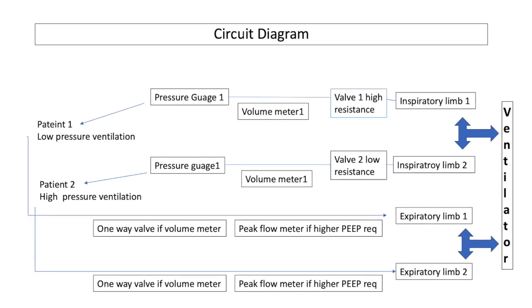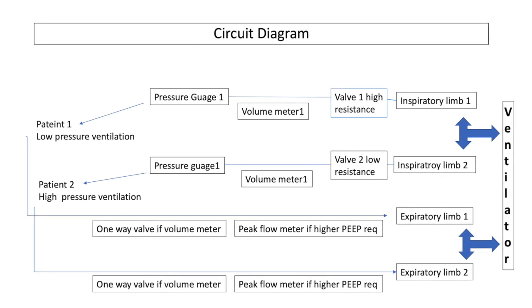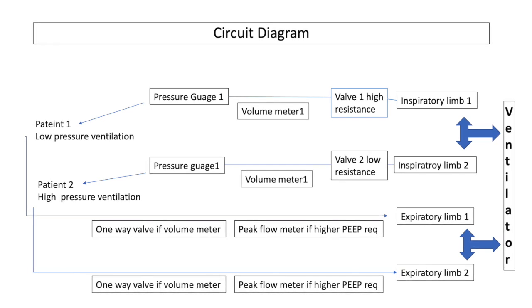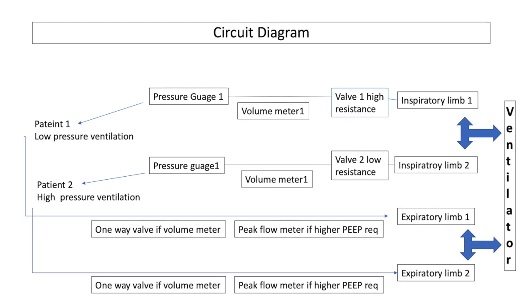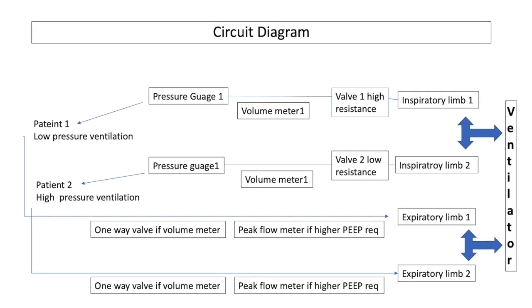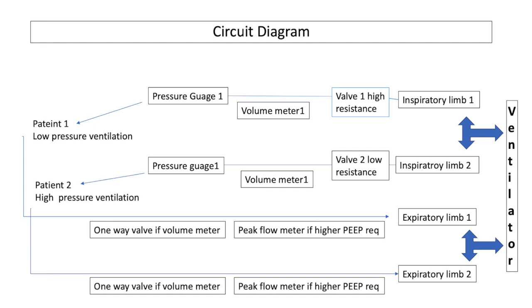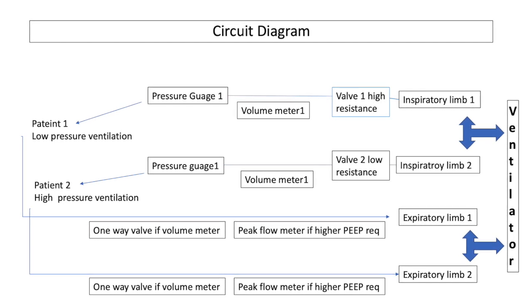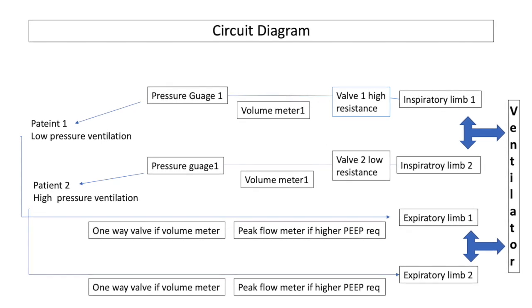Needless to say, I think the patient needs to be in the same room and there has to be constant monitoring by either a family member or preferably by a nurse or respiratory therapist of different pressures, as we would be without ventilator alarms for individual patients in this case, and most likely the alarms would be silent given we are using higher pressures. If a patient deteriorates or is not able to ventilate, the valve can be switched off and the patient can be ventilated with bag and mask without affecting any other patient till the situation is resolved.